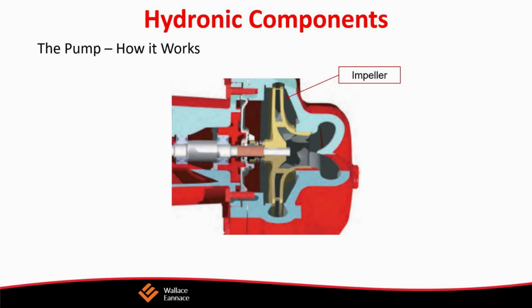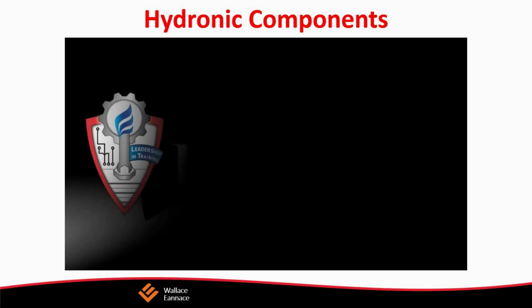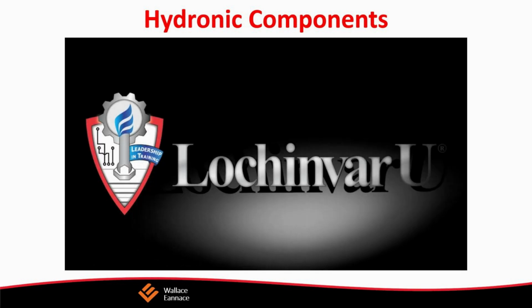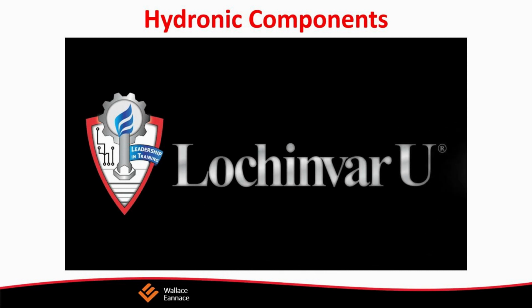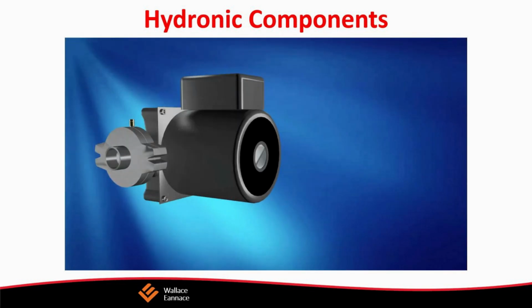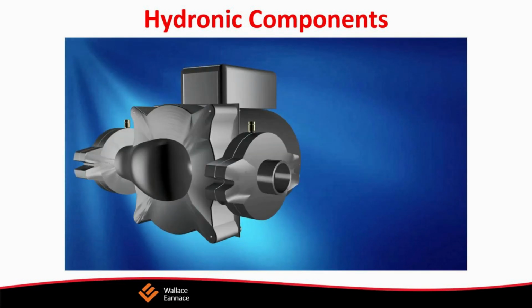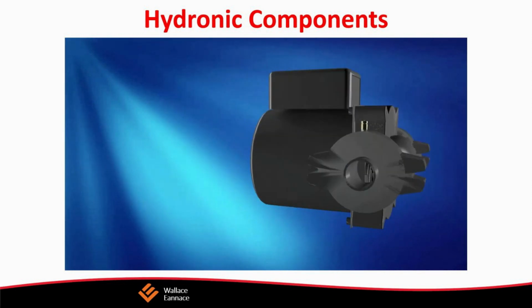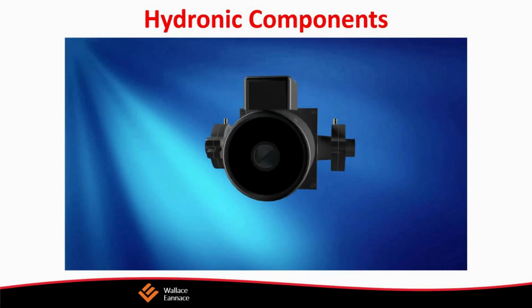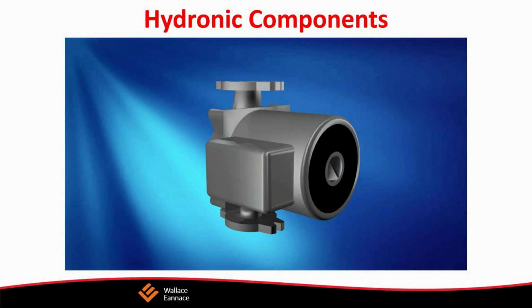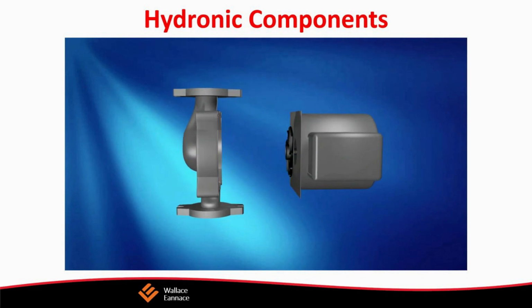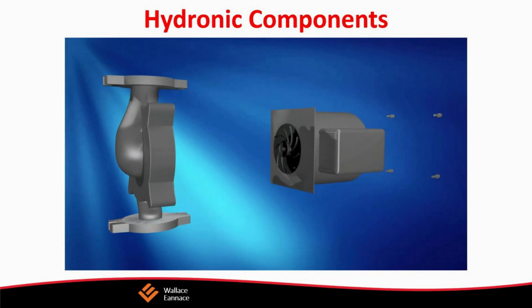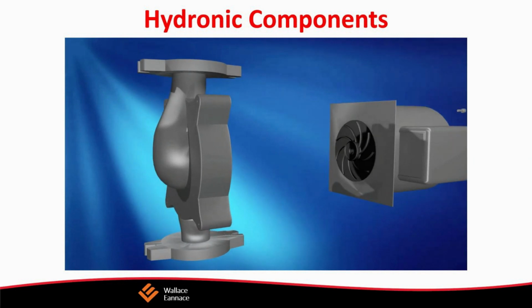And this force is measured in feet of water, typically. So 2.31 feet of head is 1 pound of pressure. When we specify pumps, we always consider the flow, which is in gallons per minute, and the amount of pressure that is put out, which is considered feet of head. And once again, 2.31 feet of head is 1 pound of pressure.